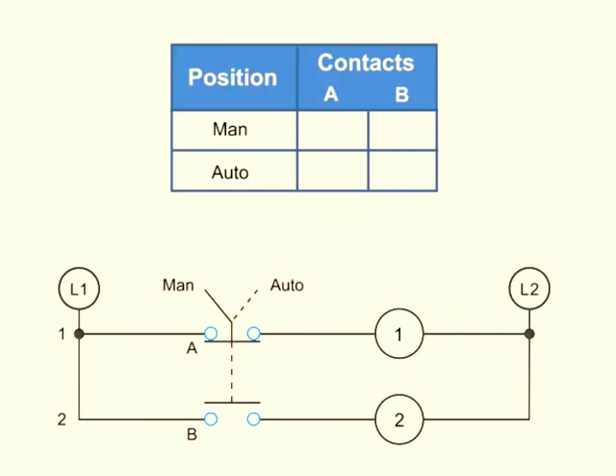The truth table can be used to easily interpret what contacts are closed for a particular position. An X is placed in the table if a contact is closed in any position; an O is used to depict that a contact is open. Thus, if the selector switch is in the MAN position, A is X or closed, and B is O or open.